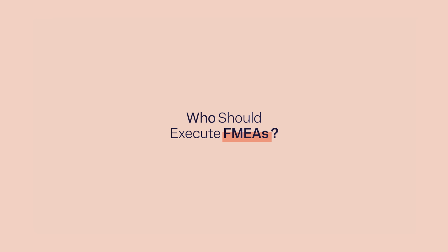The identification of failure modes and the resulting effects is based on experience with similar products or knowledge. It is important to understand that the context of use of a medical device could give different severities. For example, the use of a tensiometer with batteries has very different consequences if used underwater, right?